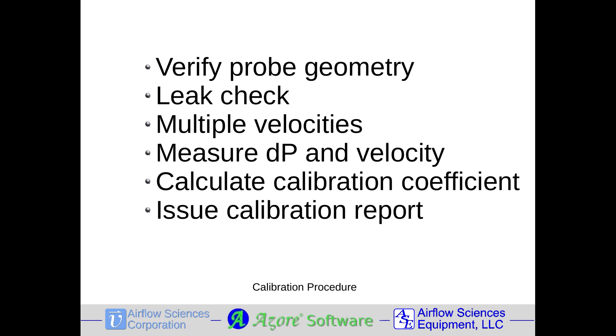First, the probe geometry is verified against EPA standards and a leak check is completed. Once the test setup is confirmed to have the correct geometry and be leak-free, the pressure measurement instrumentation is zeroed and then the wind tunnel is turned on. The calibration is generally performed at multiple velocities with three runs required at each velocity setting to verify repeatability. The key measurements are the probe differential pressure and the wind tunnel velocity for each run. After each test, calculations are performed to determine the calibration coefficient, deviation from the mean, and other required values per EPA Method 2. Finally, a calibration report documenting the raw data and calculated values is completed.